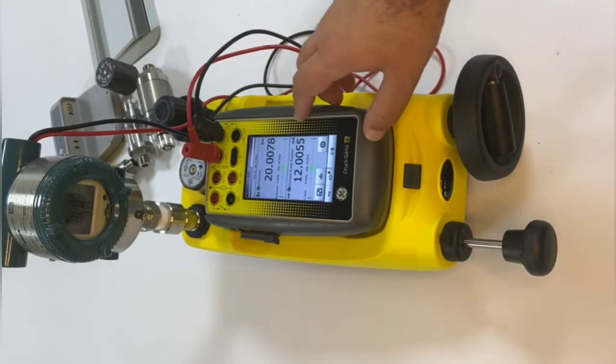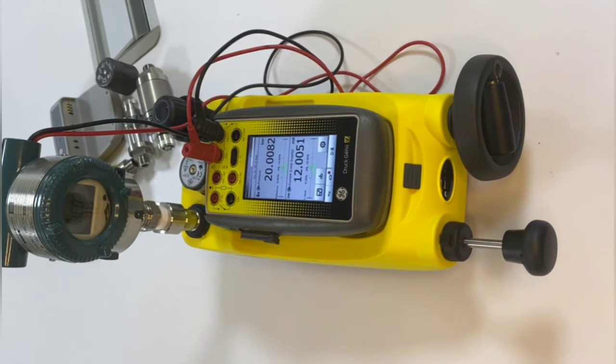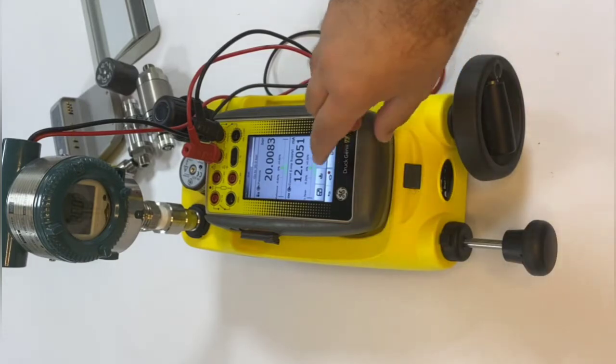And the output is within the limits. At 20 we got 12 milliamperes, it's fairly good result, it's within the tolerance.